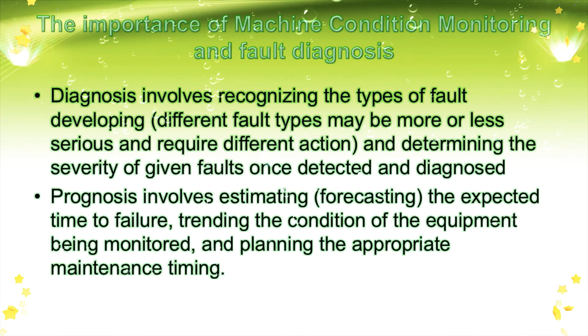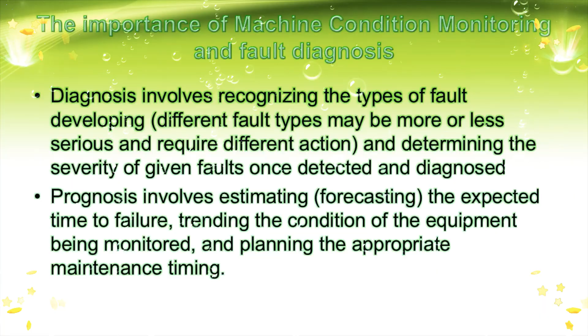The next point: diagnosis involves recognizing the type of fault developing—different fault types may be more or less serious and require different actions—and determining the severity of a given fault once detected and diagnosed. The second point is prognosis, which involves estimating and forecasting the expected time to failure, trending the condition of the equipment being monitored, and planning the appropriate maintenance timing.